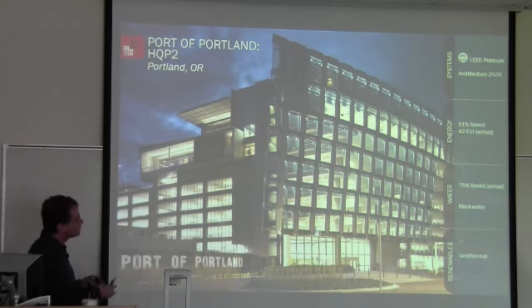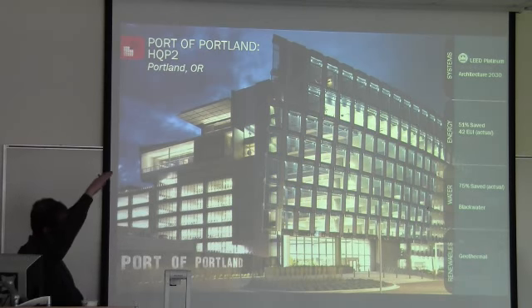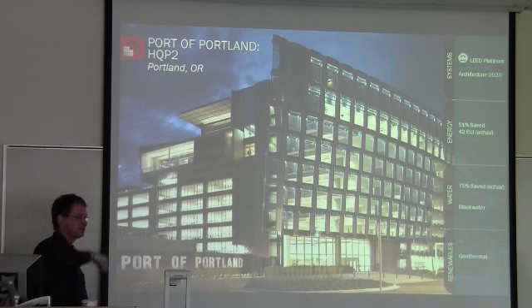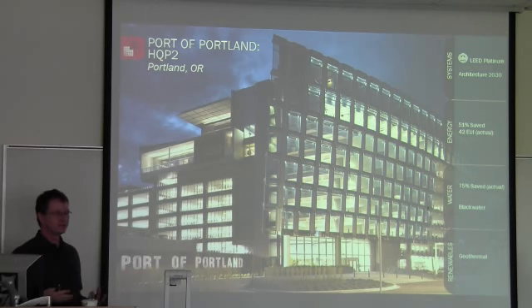So I said, well, why don't we get some spandrel panels and start reducing the actual glazing area on this wall, but yet still keep the floor-to-ceiling glass that everybody loves. When you stand in the space, it's quite dramatic to have a floor-to-ceiling glass assembly where you're looking out into the outside environment. So we drove these vertical elements, and it got rid of all of the exterior heating zone on the north side of the building.